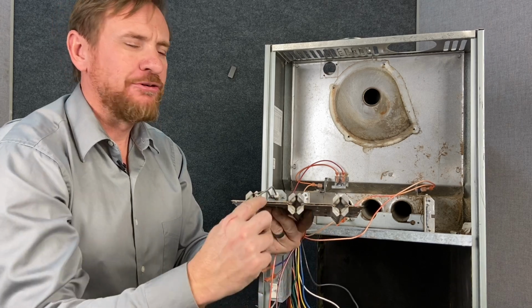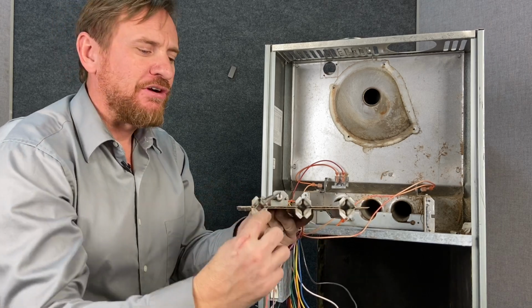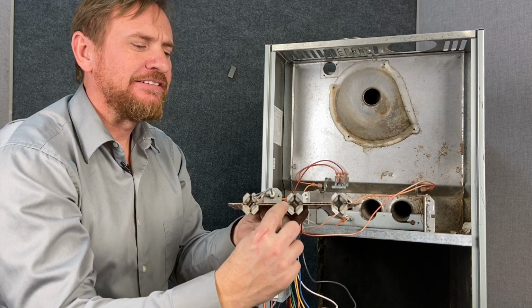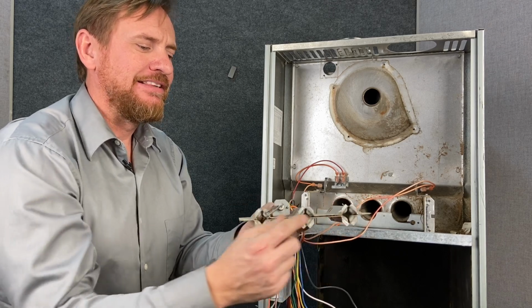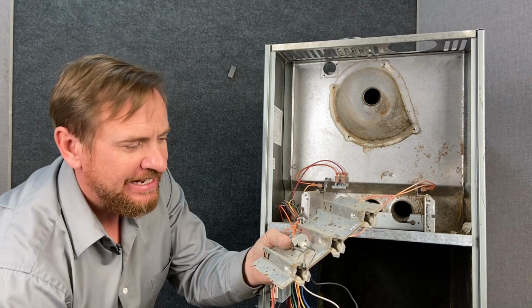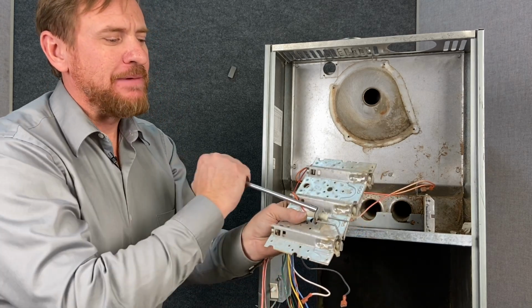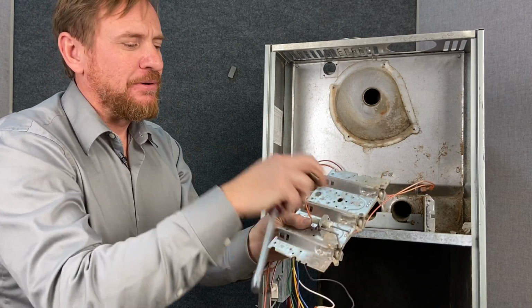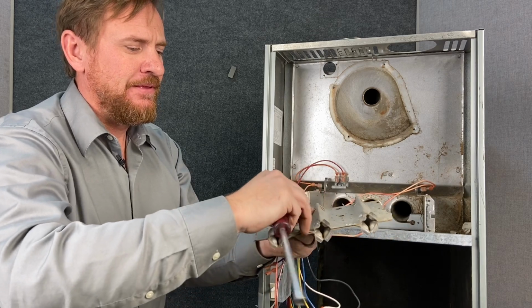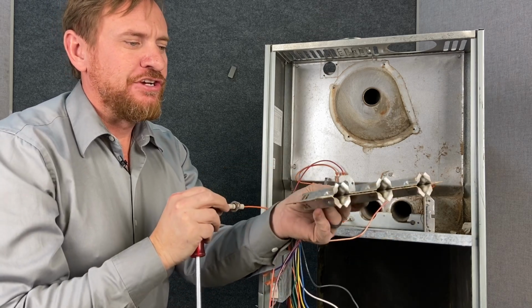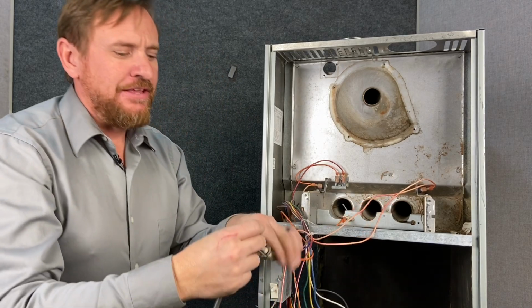Then these little tubes here are all connected. These are called crossover burners. So the main burner is coming across here and allows some gas to leak over here to light this one and then to again light this one. This is our spark igniter. It has only one wire to it. The other one is mounted to ground. If we take this spark igniter loose, that leaves just our burners.